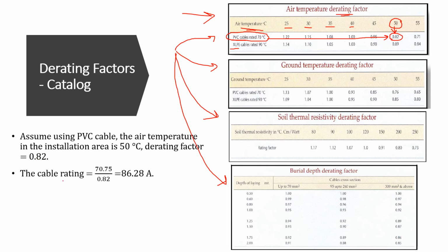So the cable rating will be the circuit breaker rated current 70.75 divided by the derating factor 0.82, which we obtained from the table. So we will need a cable rating of at least 86 ampere. Okay, so we need our cable to withstand, in these conditions, at least 86.28 ampere. So we are going to search inside the catalog for a cable which can give us this value.